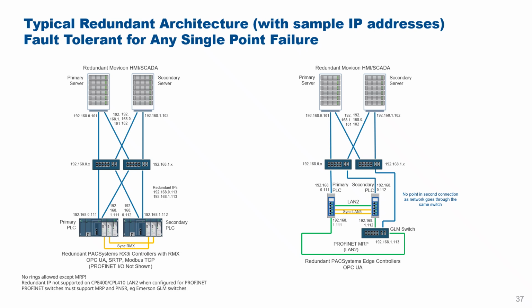So if you were using a CPE400 or CPL410 edge controller, then it could look something like this. So you'd have the same configuration at the top as before, but now you've got the issue of how do you connect to the actual PLCs. So the primary network is straightforward, 192.168.0, you've got the same connection as before. But on the secondary network, what you could do there is you could use a GLM switch, and the GLM switch allows you to connect a non-Profinet device to the Profinet ring network. So the Profinet MRP network is in green.